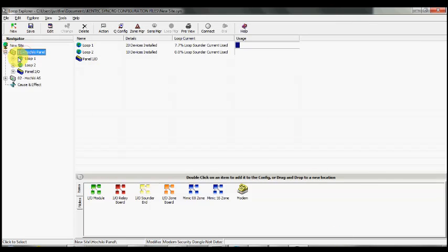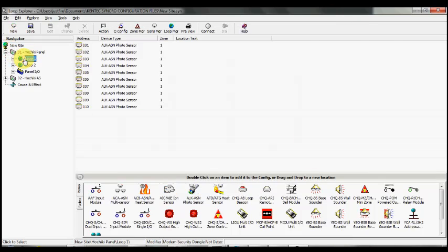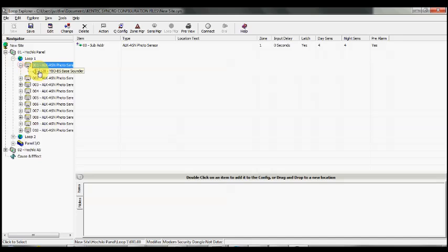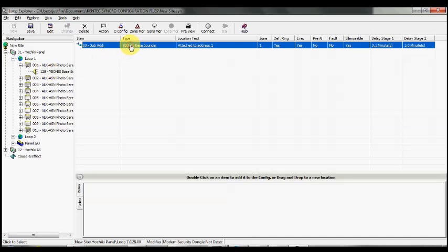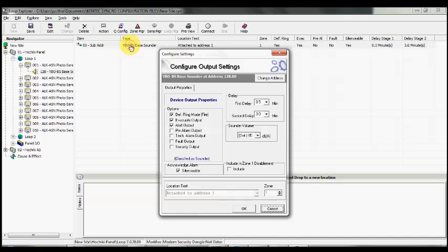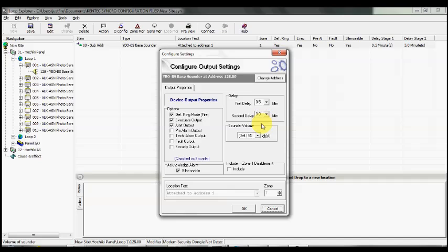Now we can take a look at the actual sounder bases and see if they've applied the settings. So we go to our loop, drop down one of our detectors, select our sounder base, double click, and you'll see that our two time periods have now been set to each of these devices.